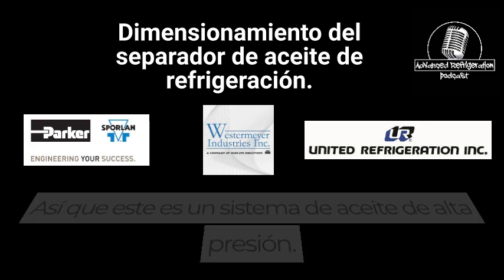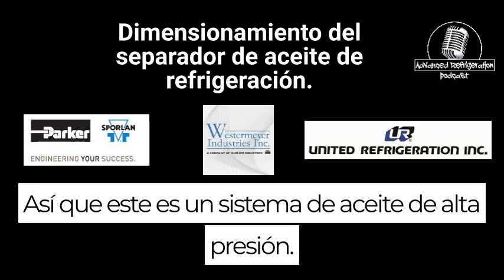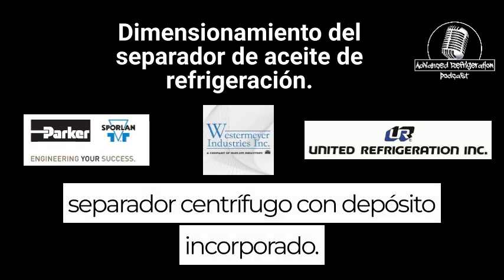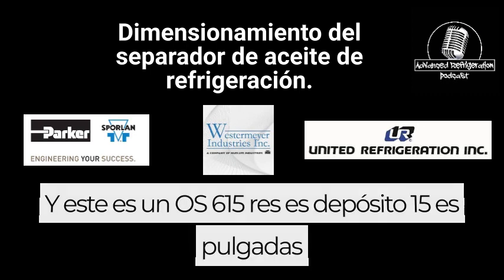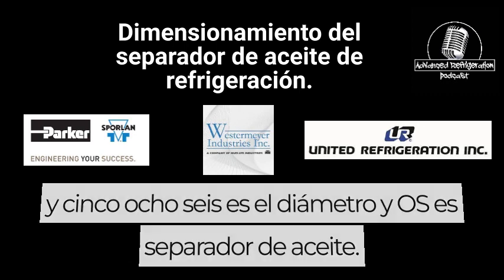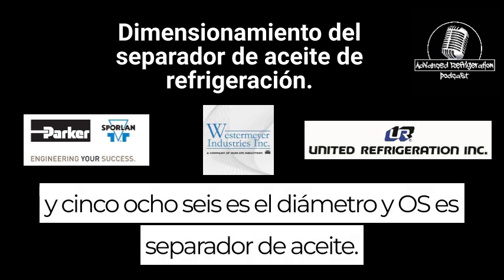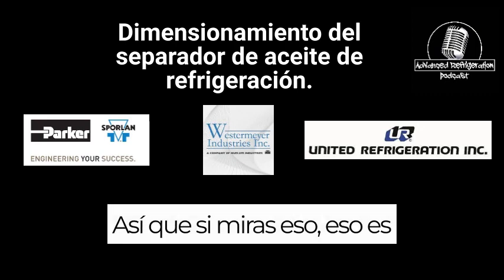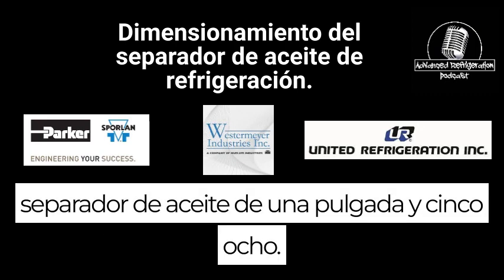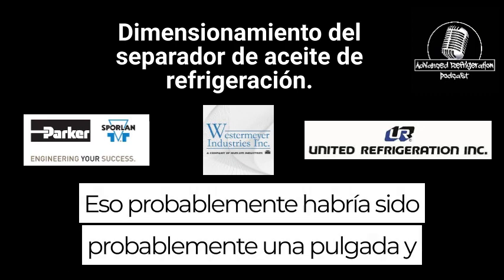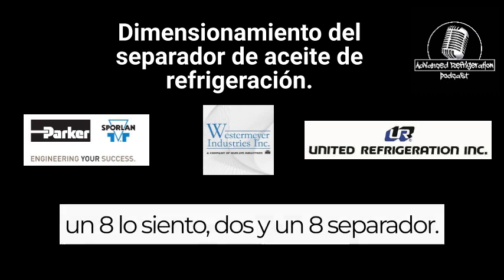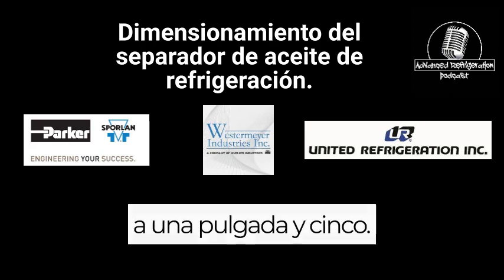So this is a high pressure oil system centrifugal separator with the reservoir built into it. And this is an OS6 15 RES. RES is reservoir, 15 is an inch and 5/8, 6 is the diameter, and OS is oil separator. So that's an inch and 5/8 oil separator. That likely would have been probably an inch and an eighth. I'm sorry, 2 and an eighth separator, whereas this one's dropping it down to an inch and 5/8.